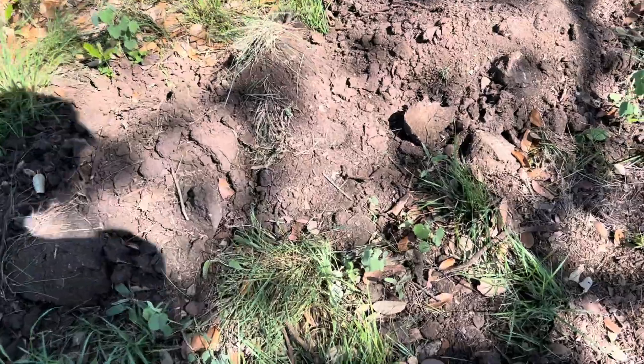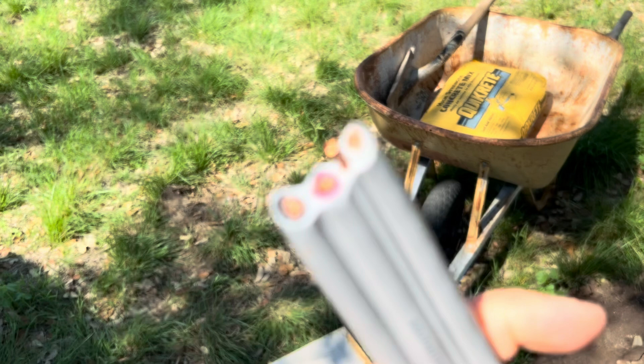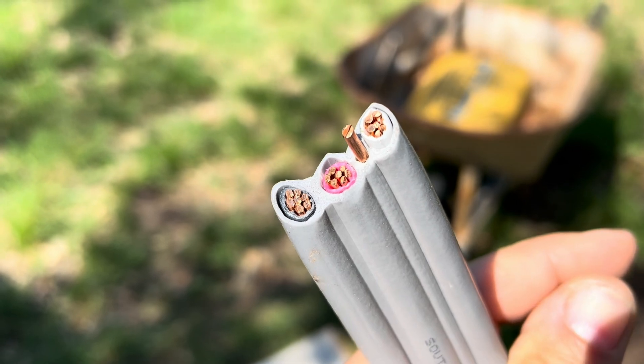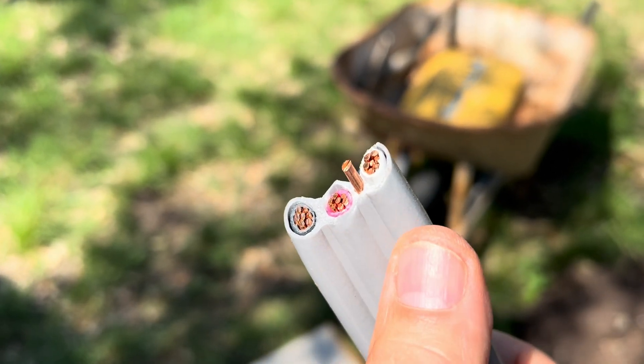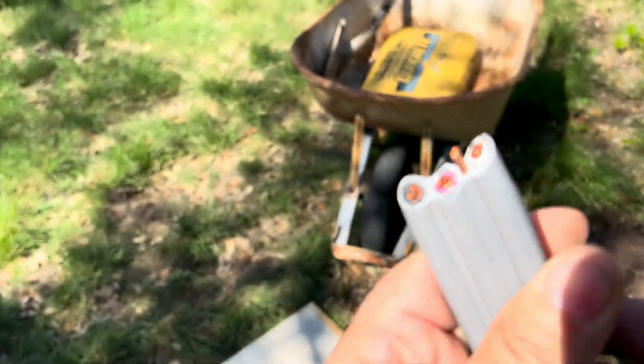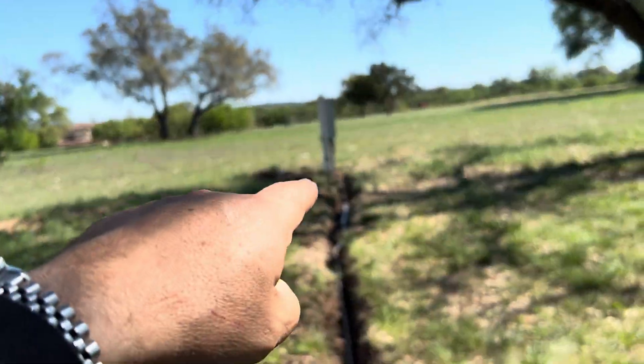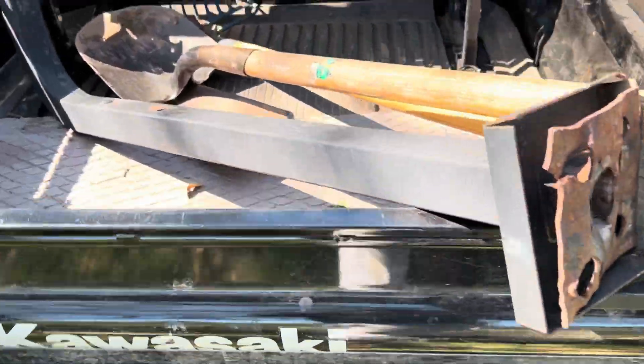The wiring here — I'm using this six-gauge cable I got on Amazon. It's really the best price I could find. It's a 50-foot length and comes with two hots: your red and black, then a white for neutral and a ground. This is a durable cable — it's got an extra coating because each wire is individually coated, and then it's also completely immersed in a really thick outer coating. I'm going to connect that up down there to the power panel and then bury it.